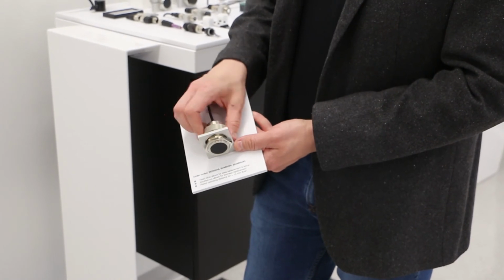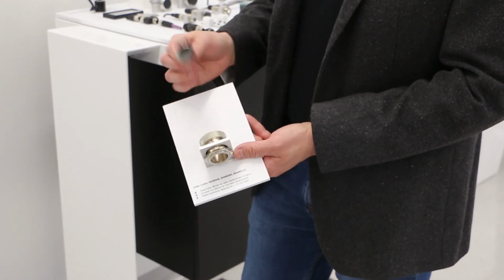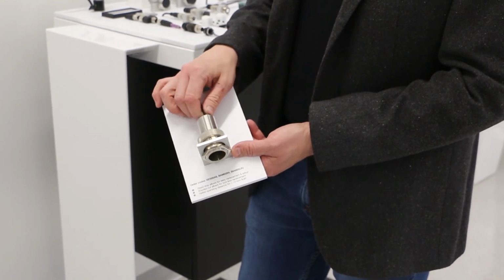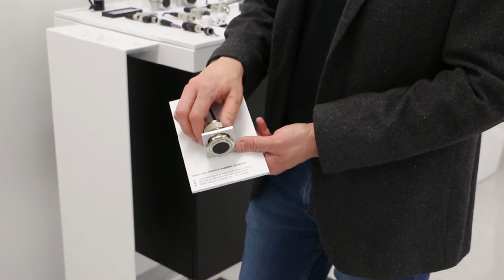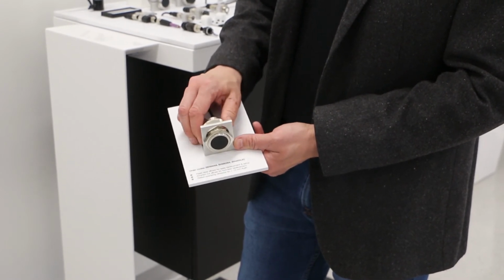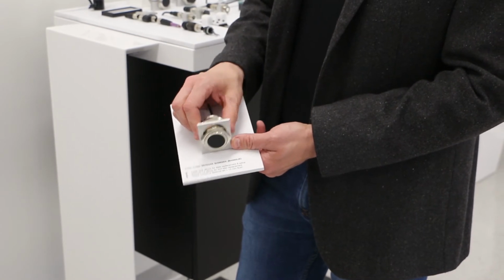I want to point out one accessory that's really interesting: our quick change mount with positive stop. This allows for easier repair on site, because a lot of people are challenged with making sure the prox is installed to the proper gap distance when it needs replacing. The quick change prox mount lets us set the gap distance for the sensor permanently. Then all you have to do is quick change a nut, take out the sensor, put in a new one, and quick change the nut back—so the sensor is gapped perfectly every time for the application. We don't have to replace the sensor, move the equipment, damage the sensor, and install a brand new one again. We get the gap right the first time, making repairs very easy in the field and on site.